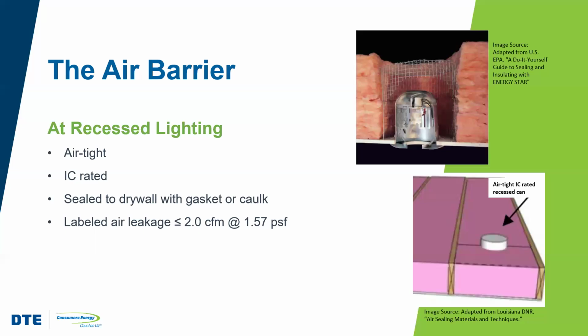Now, whether they are shielded or not, all recessed lighting fixtures installed in the thermal envelope should be rated for contact with insulation. So they should be IC rated. They should also have an air leakage rate of less than 2 CFM at 75 pascals. And a good design and construction team will ensure that there is either gasketing or, better yet, a continuous bead of caulk between the fixture housing and the ceiling drywall.